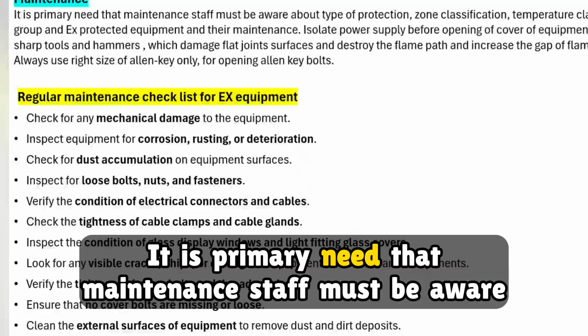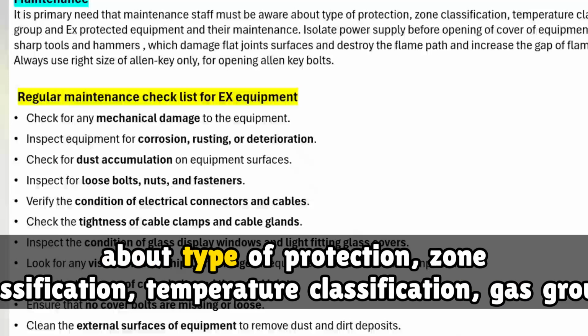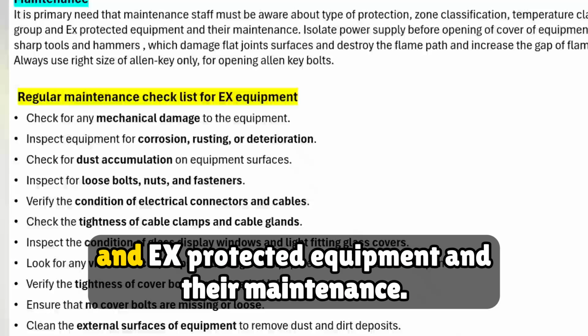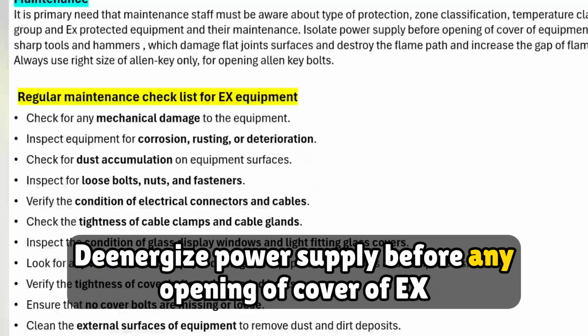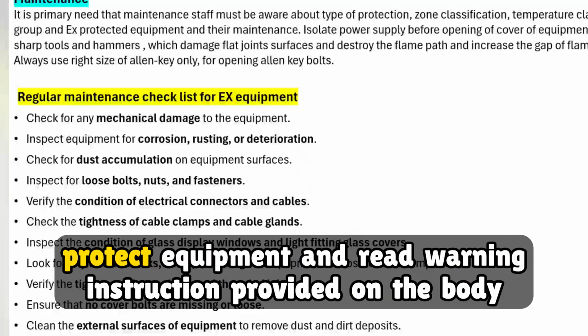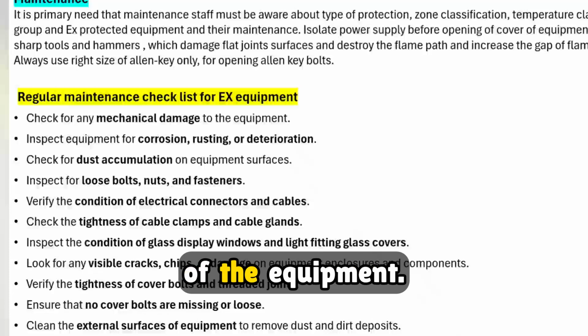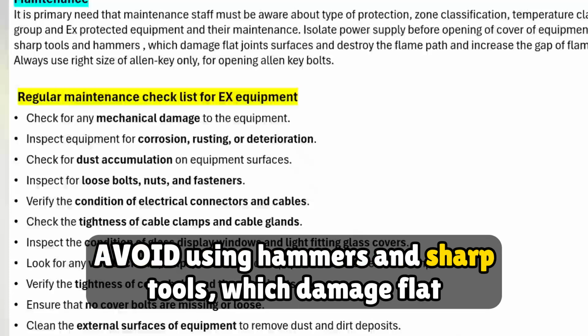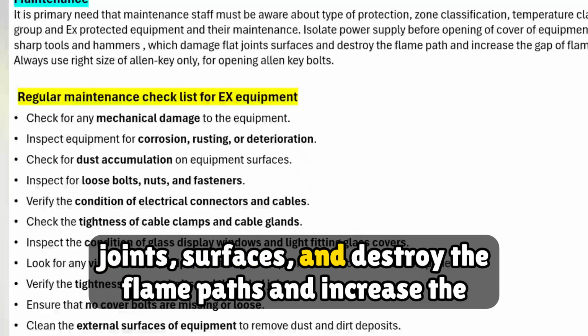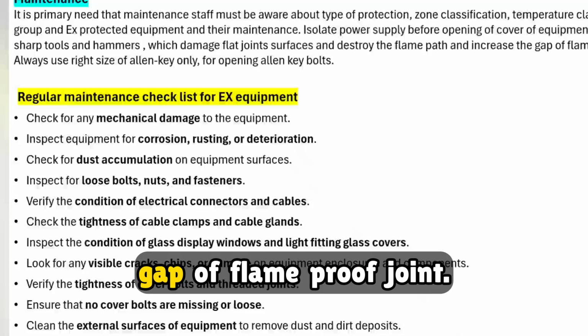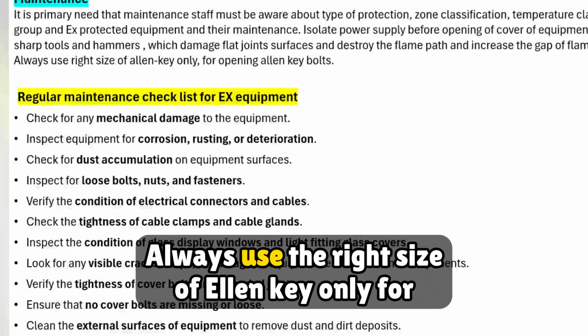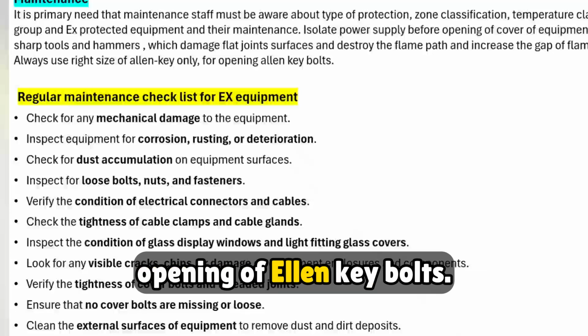It is primary need that maintenance staff must be aware about type of protection, zone classification, temperature classification, gas group, and EX protected equipment and their maintenance. De-energize power supply before any opening of cover of EX protective equipment and read warning instruction provided on the body of the equipment. Avoid using hammers and sharp tools which damage flat joints, surfaces and destroy the flame paths and increase the gap of flame proof joint. Always use right size of Allen key only for opening of Allen key bolts.